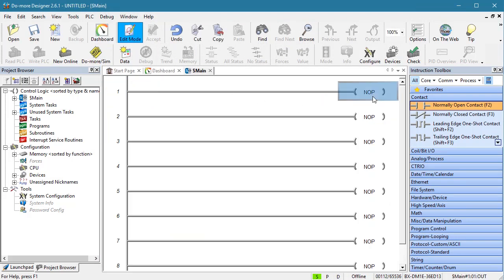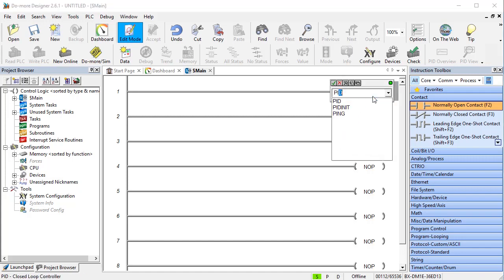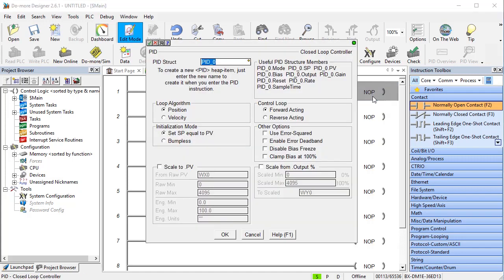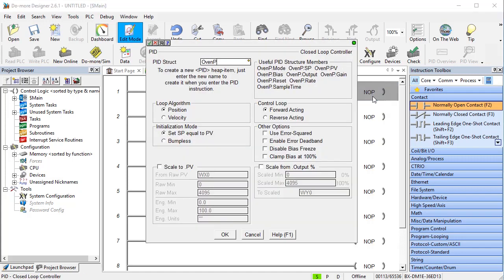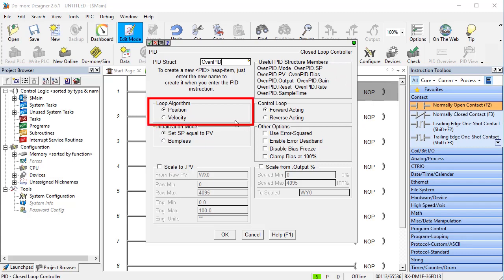Now we just put a PID instruction in our ladder code. Fill it out. We'll need a new structure – let's call it Oven PID. This is a position PID – we are monitoring the amount of heat, not how fast it is changing. Be careful here – if you are measuring a motor speed for example, do you choose position or velocity?